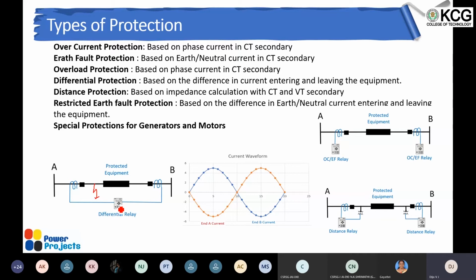Earth fault protection works in a similar way. There we give the relay an earth fault measurement CT, or we do a residual connection of all the phase CTs: we add all the phase CTs together, and the resultant goes into the relay. That means IA plus IB plus IC is nothing but the earth fault current 3I0. That goes into the relay, which is used for protecting against earth faults on the protected equipment.